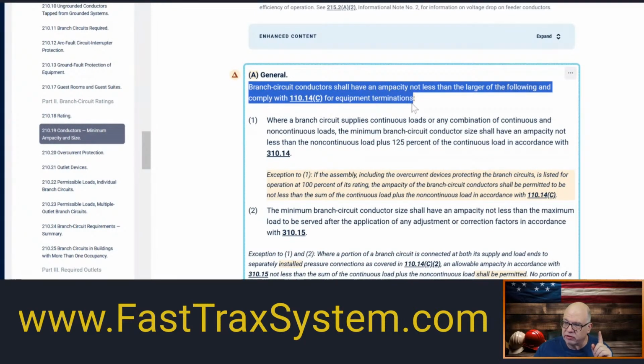110.14(C) for equipment terminations. Now, y'all remember 110.14(C), that is your 100 amps or less and then over 100 amps, right? That type of thing, or 14 through 1 gauge, that kind of thing is 60, and then over that is 75. Y'all get that, right? That's your terminal, that's your equipment termination rules that we have to follow, unless everything is marked. So if the terminals are 75 and the load terminals are 75 and the wire is rated at least 75 or higher, then you can ignore the 60-degree ampacity column for normal wiring, not for non-metallic sheath cable, but for normal wiring applications, you can ignore the 60, right? Because everything is rated for 75 or greater. You get me? Okay, so that's kind of that allowance back there.